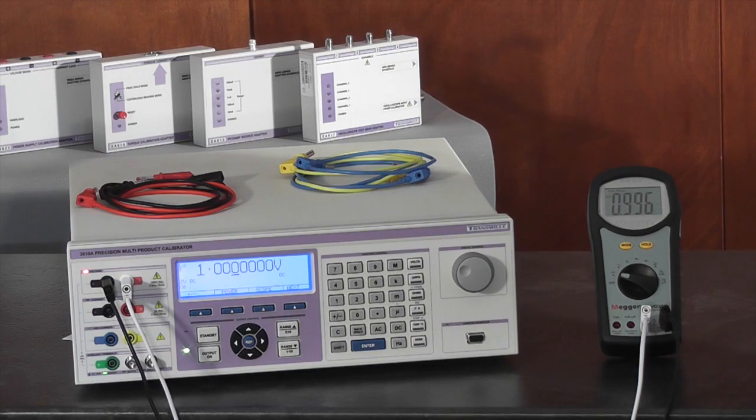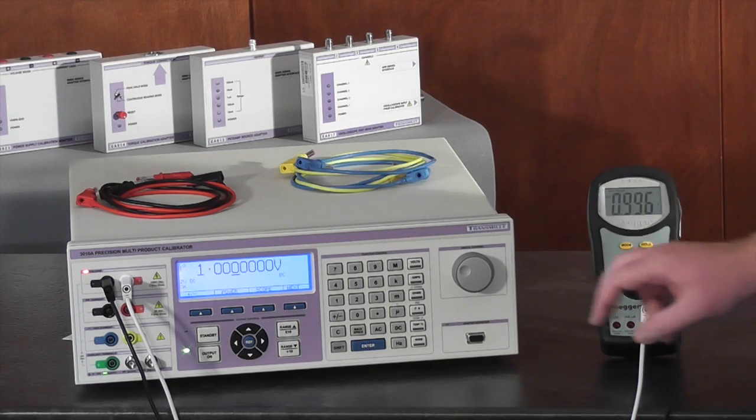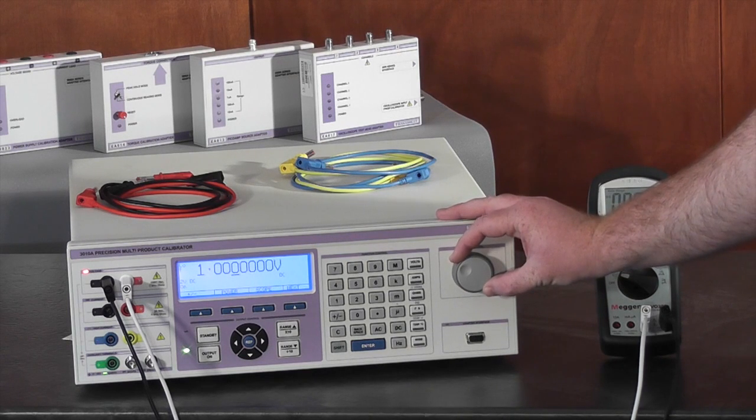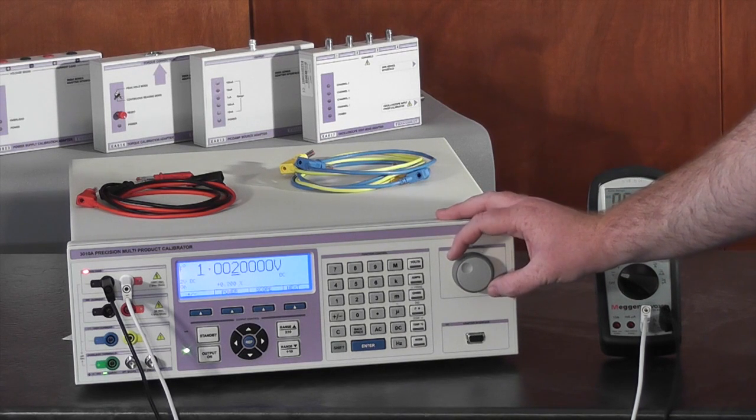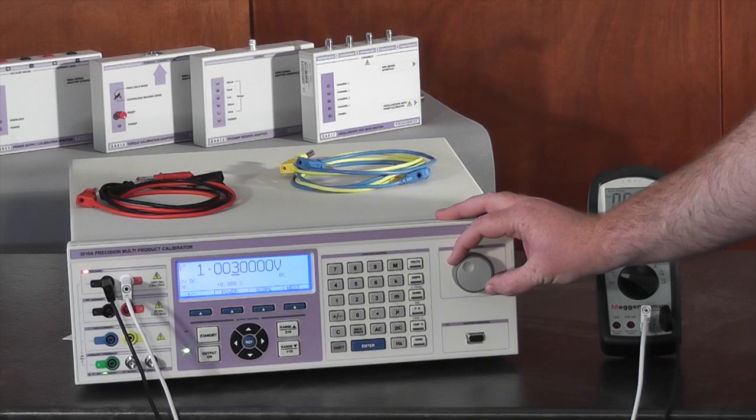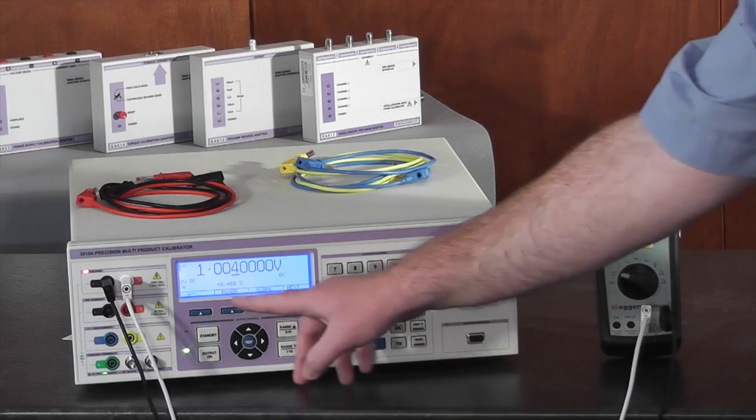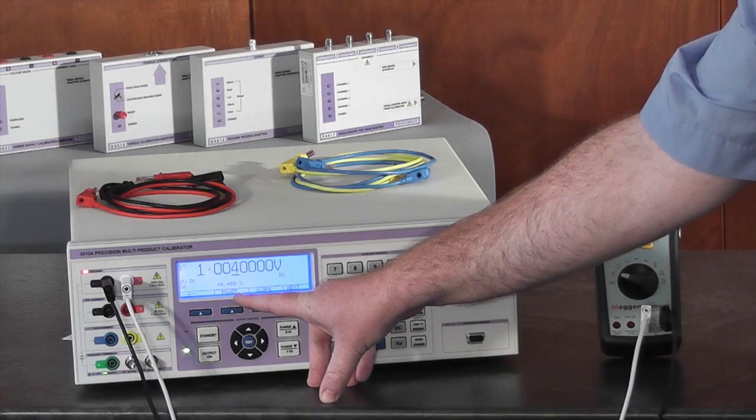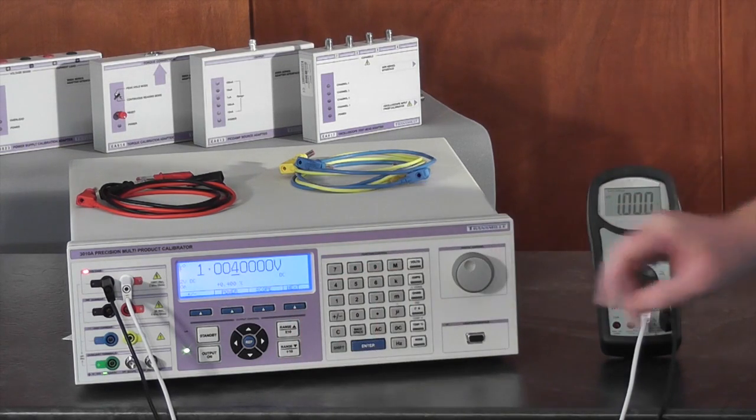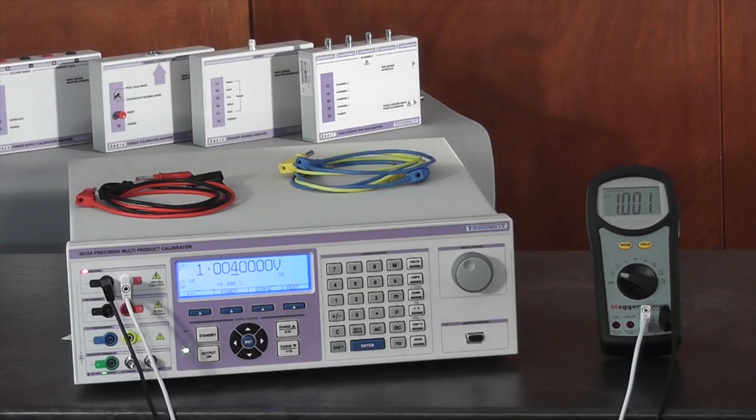To work out the error of the multimeter, you can simply deviate the output of the calibrator until the multimeter reads the correct value. This multimeter has an error of 0.4%. We will now proceed to testing AC voltage.